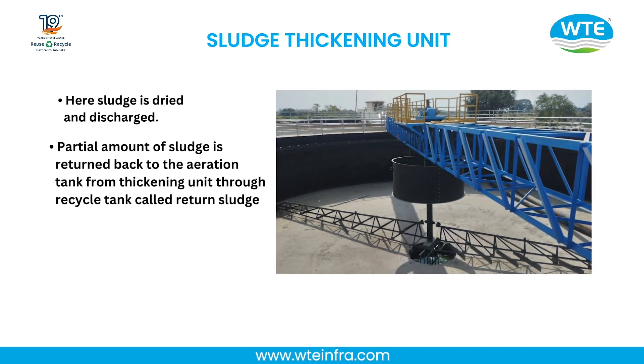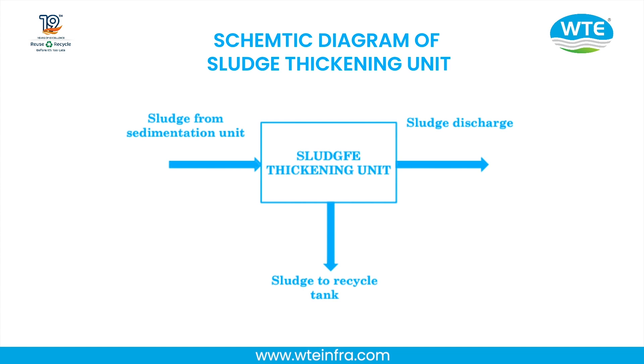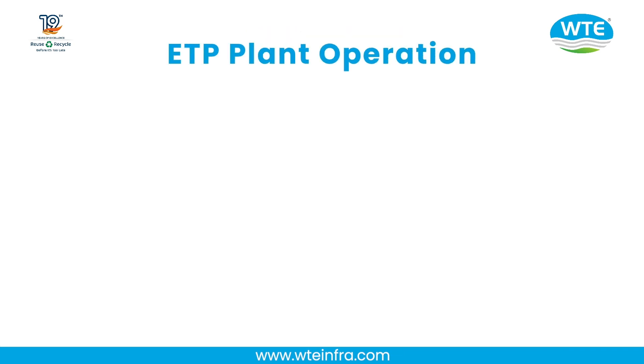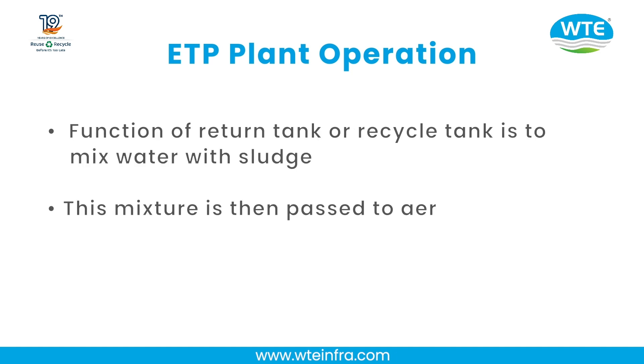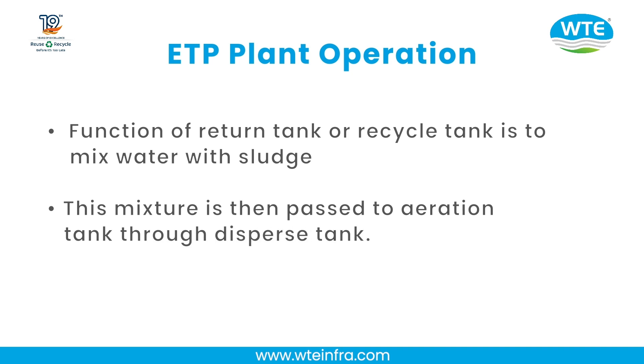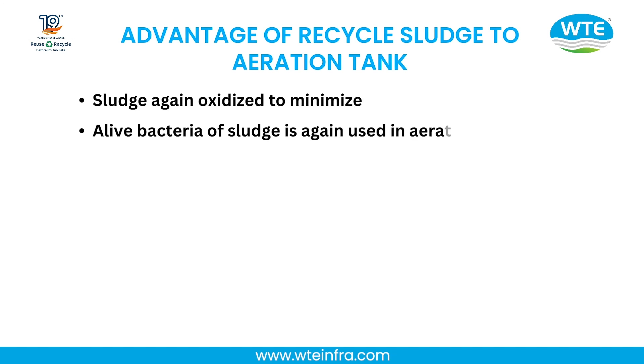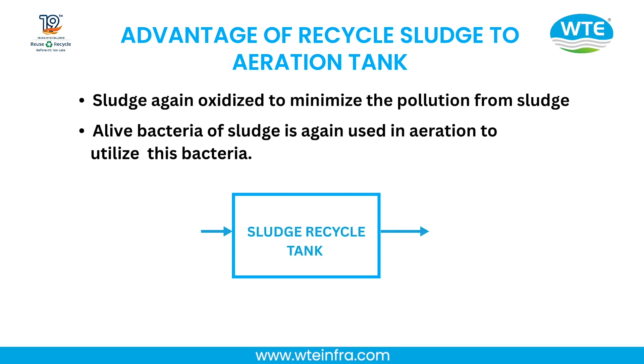Sludge Thickening: A partial amount of sludge is returned back to the aeration tank from the thickening unit through the recycle tank (written sludge tank) and dispersed tank. The function of the recycle tank is to mix water with sludge; this mixture is then passed to the aeration tank through the dispersed tank. Advantages of recycled sludge: sludge is again oxidized to minimize pollution, and live bacteria from the sludge are reused in the aeration tank.